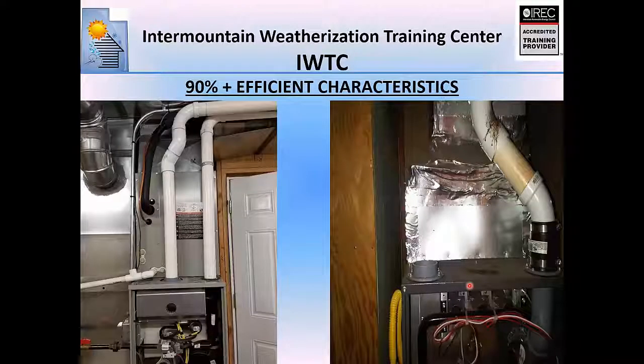Okay, and then of course here we have 90% efficient. And the giveaway here is the flues. If you've got plastic flues of some sort, then that means the flue temperatures are so low that it's super efficient. It's taking all the heat energy out of the gas, putting it in the house, thus causing lower flue temperatures. So we've got exhaust and intake, and they should both run to the outdoors. That's the proper way to do it.